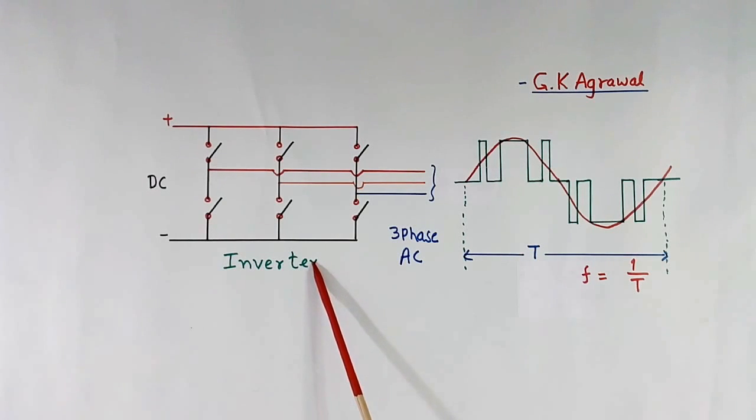This is inverter which converts DC into 3-phase AC. You may be aware of 3-phase rectifier which converts AC into DC, but inverter is reverse type. It converts DC into AC. There are 6 switches. These are IGBTs. They will be becoming on and off in sequence. If this becomes on, we get positive voltage here. I have shown here in green color. If this becomes on, we get negative voltage here. So these switches will be becoming on and off. I have shown only 1, 2, 3, 4, 5, 6 times becoming on and off. Actually it may be becoming on and off many times. When you filter this green color, you get red color which is AC.